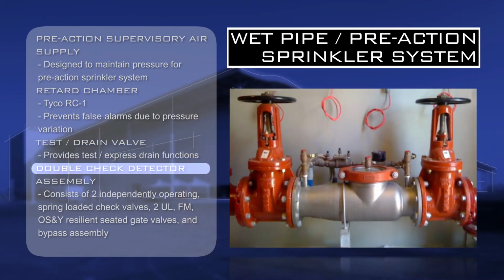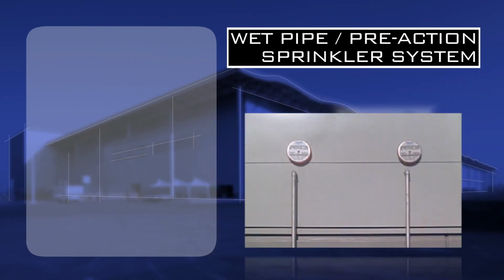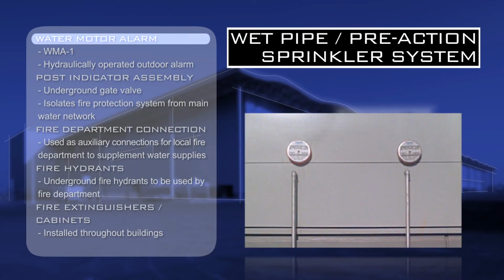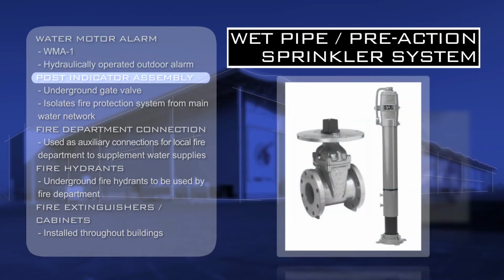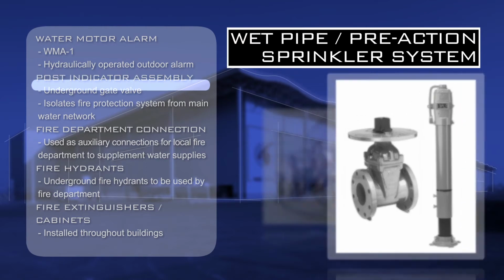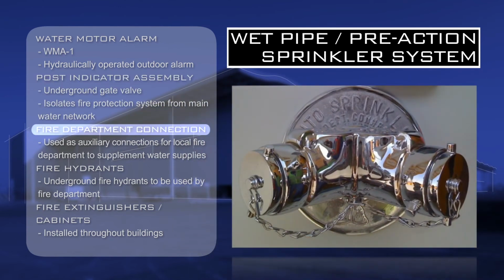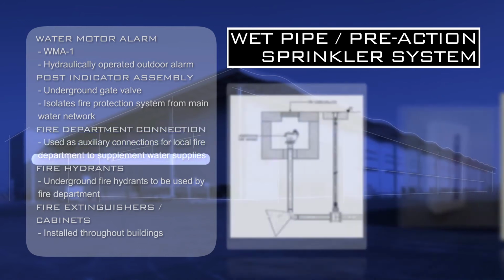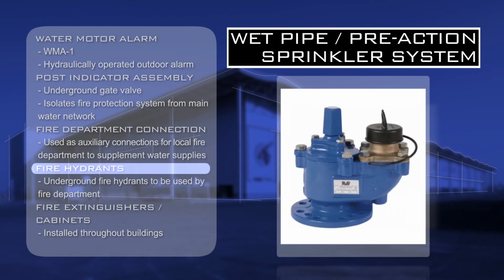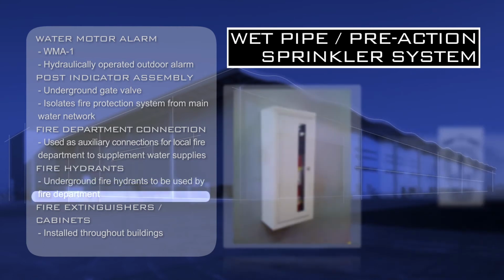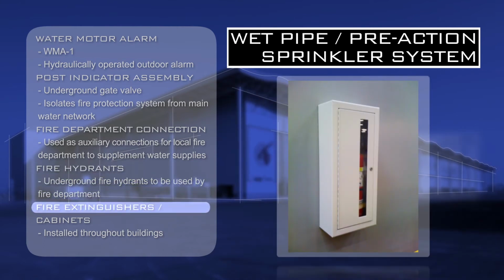The double-check detector assembly consists of two independently operating spring-loaded check valves, two UL, FM, OS and Y resilient seated gate valves, and bypass assembly. The water motor alarm is hydraulically operated. The post indicator assembly is an underground gate valve and isolates the fire protection system from the main water network. The fire department connection is used as an auxiliary connection for the local fire department to supplement water supplies. Fire hydrants are underground and to be used by the fire department. Fire extinguishers and cabinets are installed throughout the buildings.